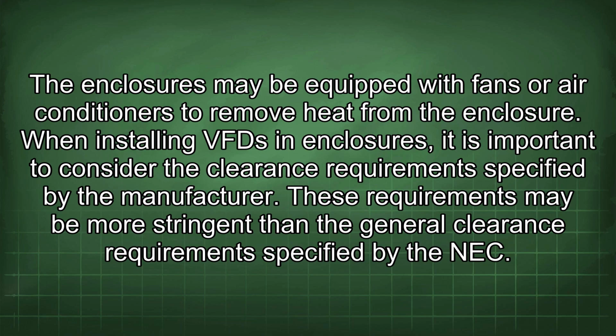When installing VFD enclosures, it is important to consider the clearance requirements specified by the manufacturer. These requirements may be more stringent than the general clearance requirements specified by the NEC.